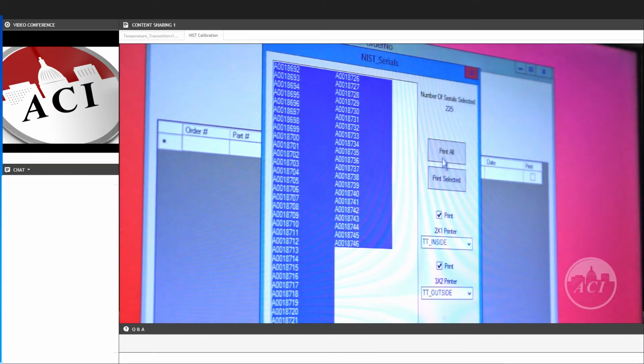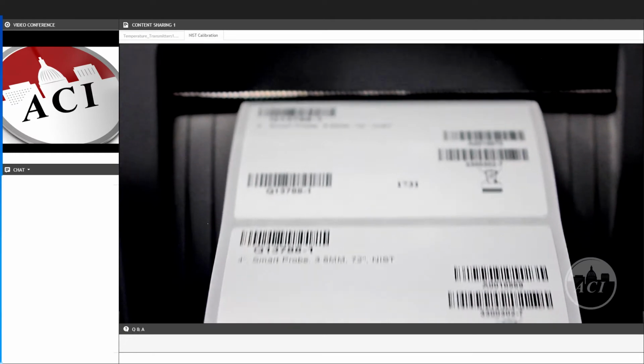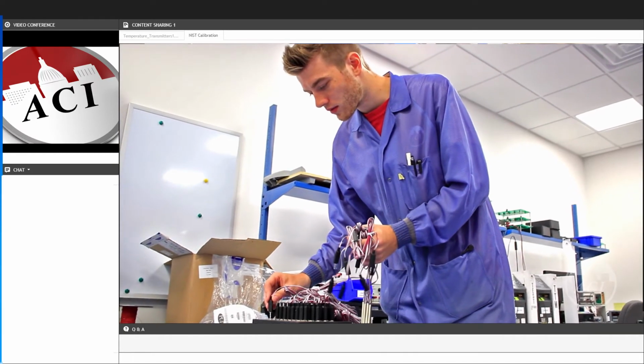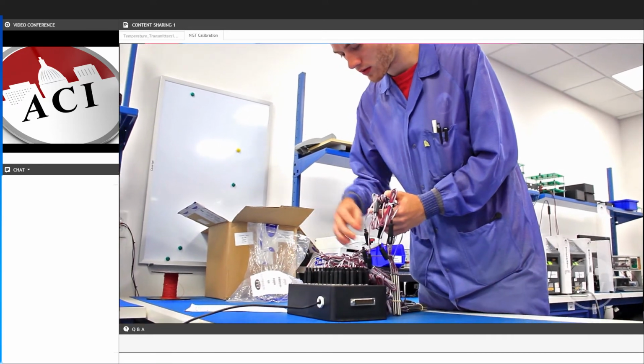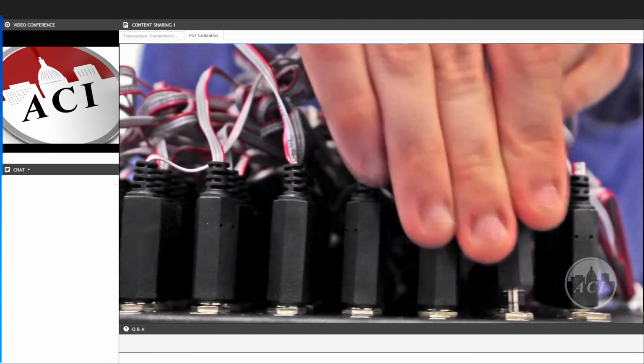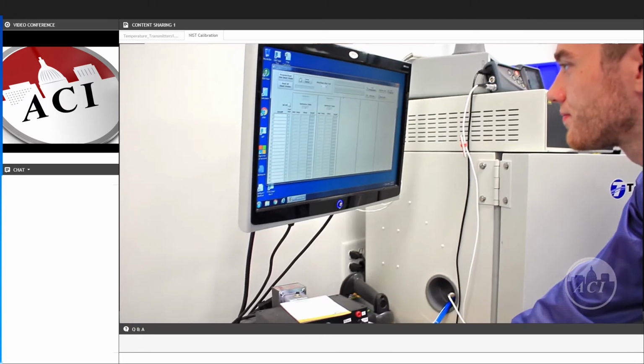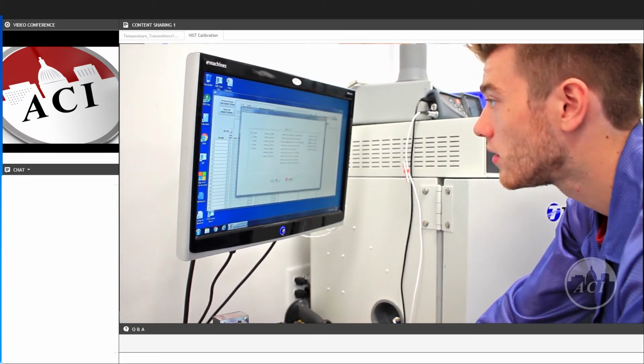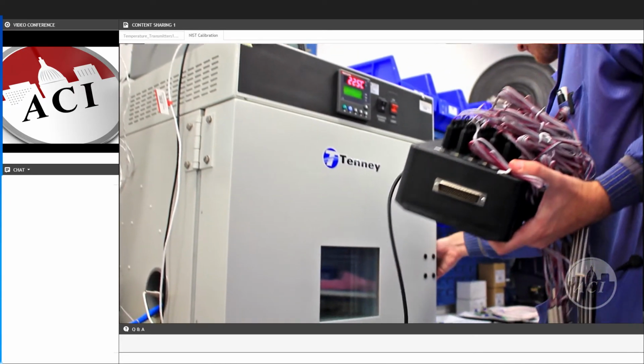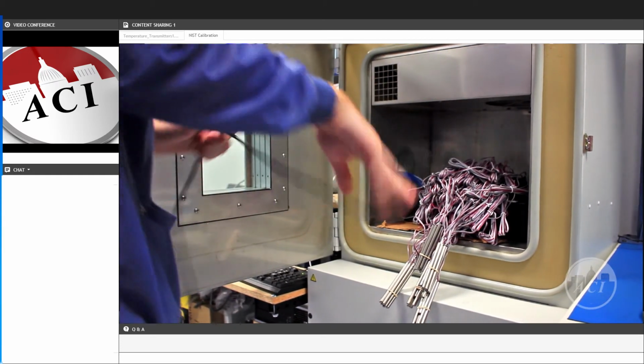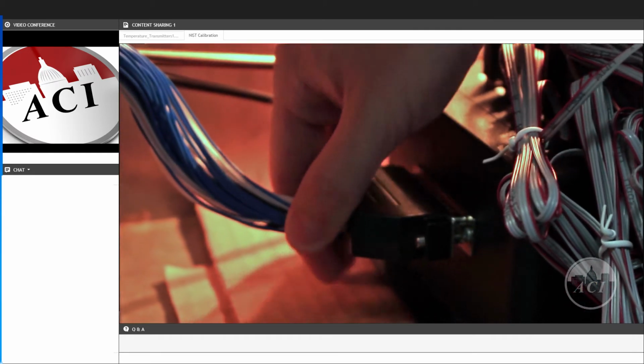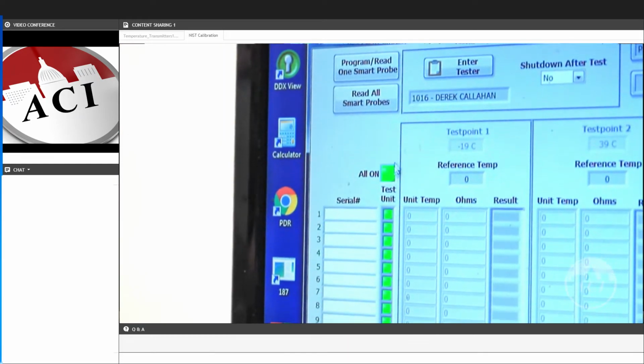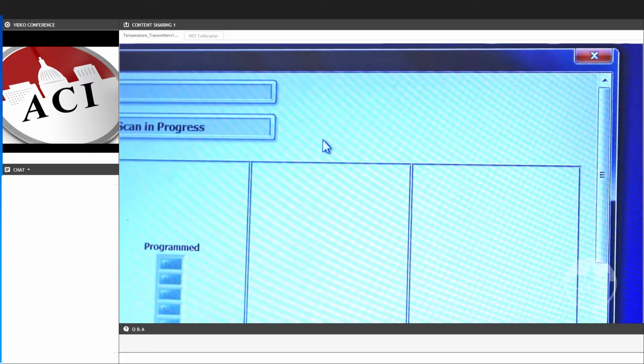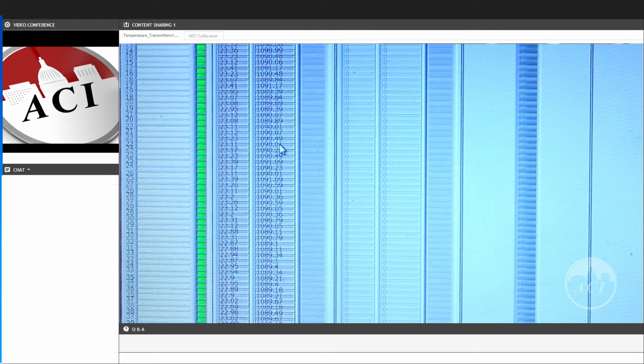Here's Derek, who's the supervisor for our temperature transmitter department, preparing some sensors to go into the NIST chamber. And when we do this, every sensor is individually serialized so that its testing can be documented and traced. We also provide the specifications of the testing chambers that we use for these NIST certificates. So here we've got some OEM temperature transmitters that are going into the chamber, and our proprietary software is going to log the test results and determine whether they're within or without the stated accuracy specifications.